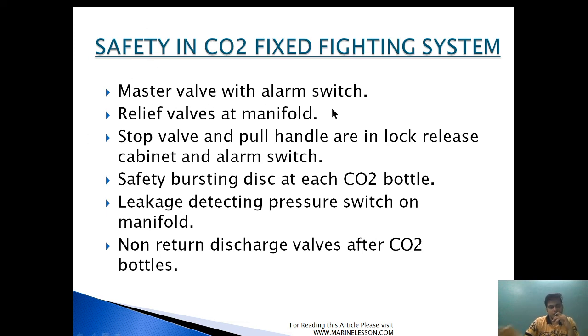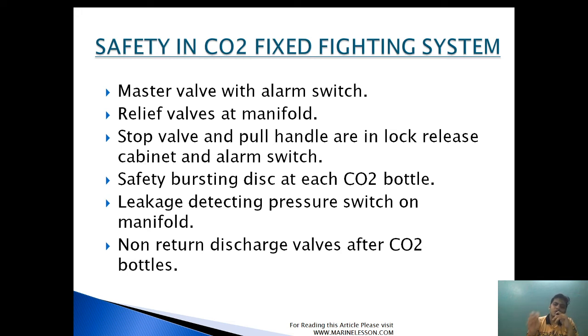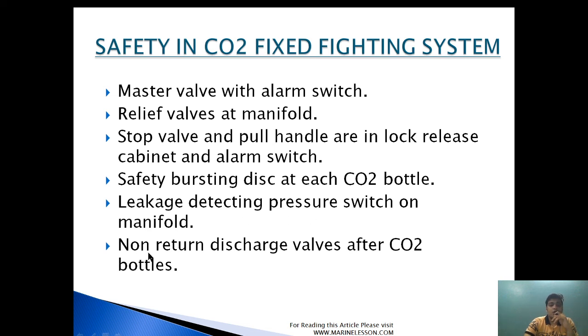Safety features of the CO2 flooding system include: the master valve with an alarm switch, which is a pressure type alarm that continues as long as CO2 passes; a relief valve in the manifold; a stop valve and pull handle, all in a lock-release cabinet with an alarm switch that activates when the cabinet door is opened; safety bursting discs at the CO2 bottle, which burst to release excess pressure if temperature increases; a leakage-detecting pressure switch on the manifold; and a non-return discharge valve. Each safety feature will be explained in detail in the next video.